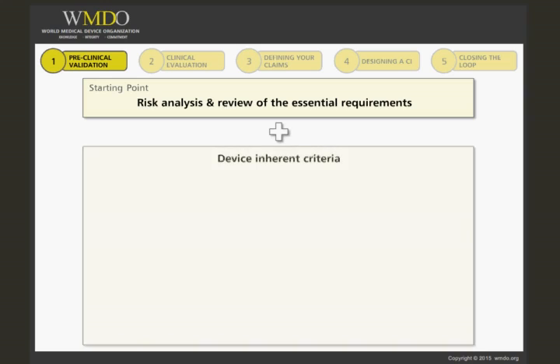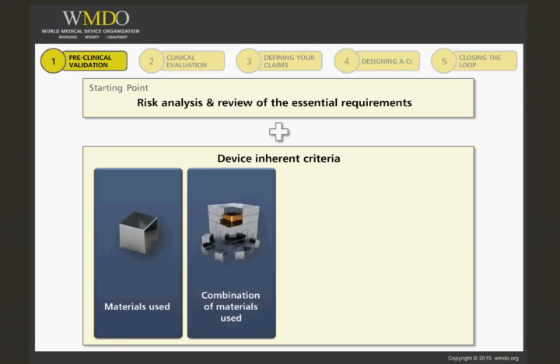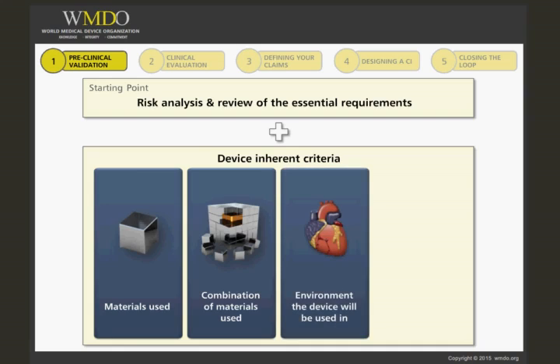The extent of your preclinical validation depends on several device inherent criteria. The materials used, that is, is there a known biocompatibility. The combination of materials used, that is, two biocompatible materials used together may become toxic. The environment the device will be used in, that is, in contact with body tissue or body fluids.